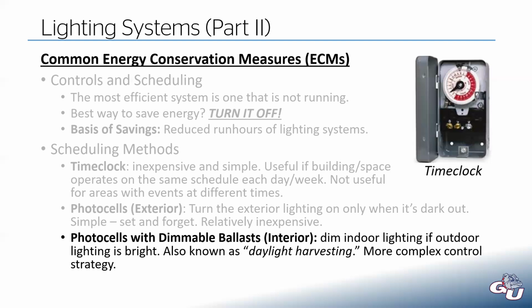So if you have a bunch of windows that are, say, facing south, and in the middle of the day you get tons of sunlight, you probably don't need to operate all of your light fixtures. And if you have smart enough controls that can dim those lights, you target a certain number of foot candles. That way it's a dynamic change in the light output from your fixtures to give you just what you need. So that control strategy is a little more complex.